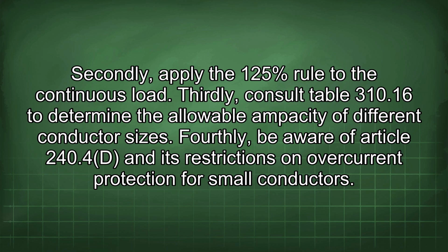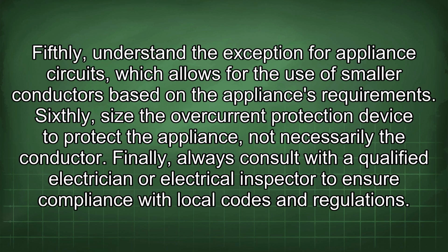Fourthly, be aware of Article 240.4d and its restrictions on overcurrent protection for small conductors. Fifthly, understand the exception for appliance circuits, which allows for the use of smaller conductors based on the appliance's requirements. Sixthly, size the overcurrent protection device to protect the appliance, not necessarily the conductor. Finally, always consult with a qualified electrician or electrical inspector to ensure compliance with local codes and regulations.